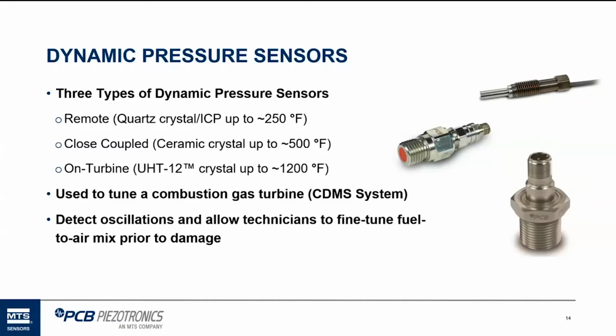Typically, these sensors, when they're mounted on the gas turbine, are used to tune the gas turbine. Sometimes they're just turned on to tune a turbine twice a year, then they turn it off and they never really look at the data again. Some companies monitor the combustion dynamics all the time. All of these sensors are used to detect oscillations when the turbine's running, and then these technicians, typically called tuners, are able to go out and fine tune the gas turbine's fuel and air mix so they can get that optimum, so there's no damage to the gas turbine, along with meeting emission standards and fuel consumption.